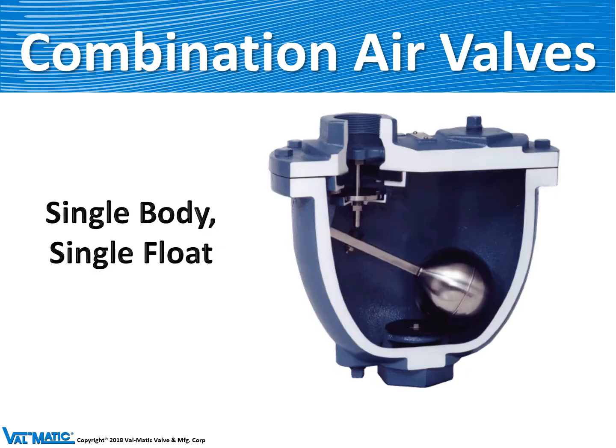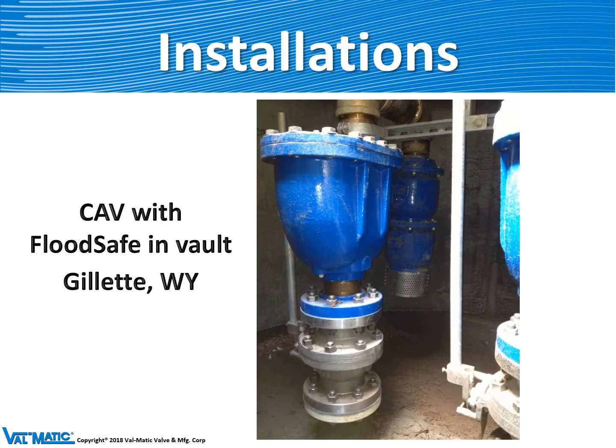This is a photograph of a Model 201C single body combination air valve, which you can see has a single float. It's made typically of cast iron with all type 316 stainless steel trim. Here is one mounted in a vault in Gillette, Wyoming, and it also has a FloodSafe mounted behind it to protect the air valve from floodwaters.